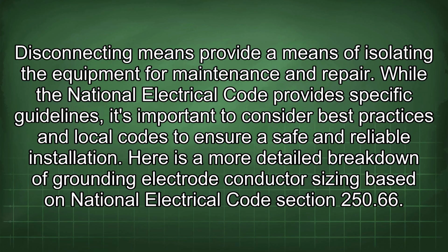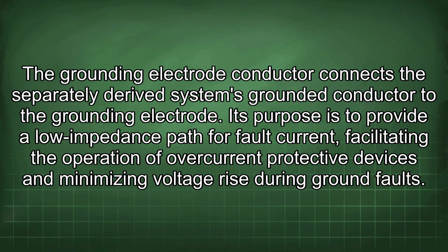While the National Electrical Code provides specific guidelines, it's important to consider best practices and local codes to ensure a safe and reliable installation. Here is a more detailed breakdown of grounding electrode conductor sizing based on National Electrical Code Section 250.66. The grounding electrode conductor connects the separately derived system's grounded conductor to the grounding electrode. Its purpose is to provide a lower impedance path for fault current, facilitating the operation of overcurrent protective devices and minimizing voltage rise during ground faults.